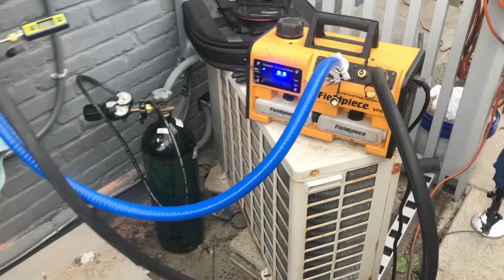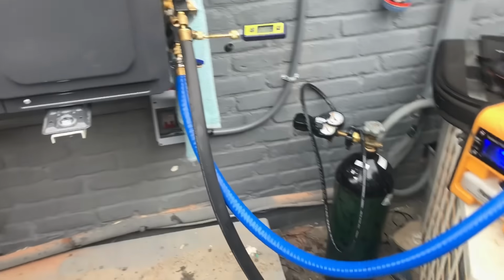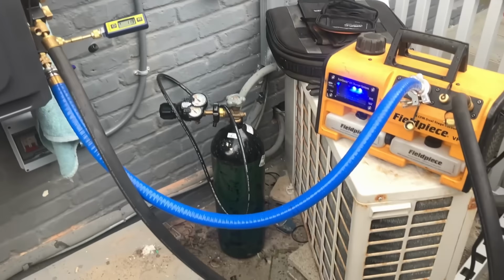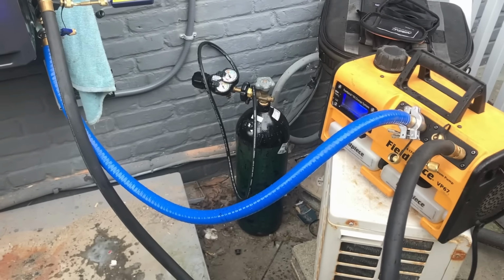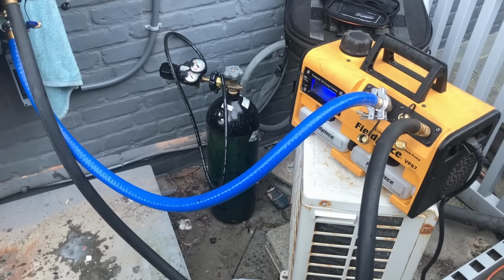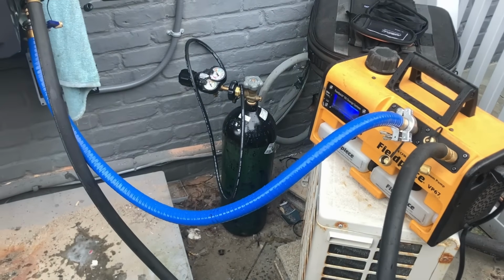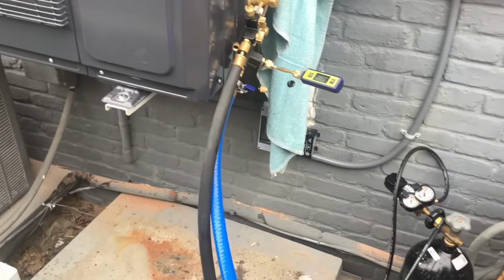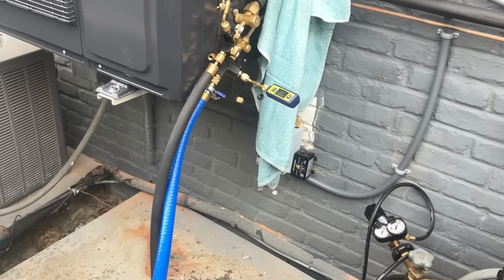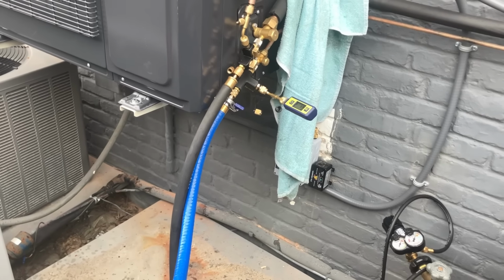So, you guys are in the HVAC trades. You guys are probably familiar with these hoses. Hopefully you are. We use large diameter vacuum hoses. We remove the Schrader cores, right? We connect directly to the system, and we are pulling the deepest vacuum we can. Then we isolate the system. We'll perform a decay test. If it won't hold, right, that means something's wrong.